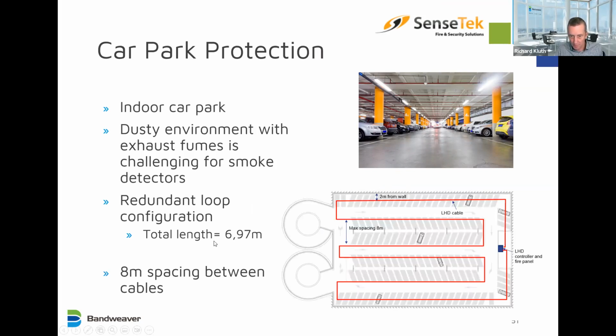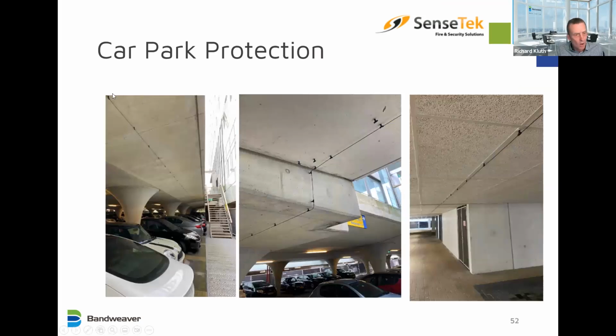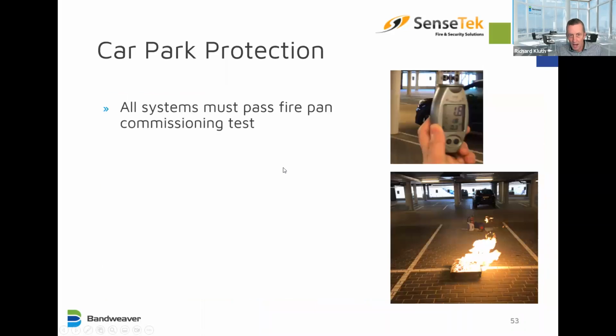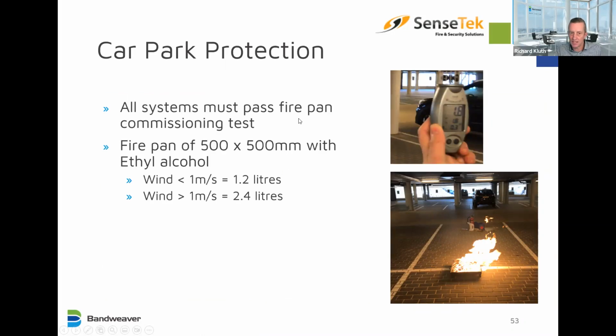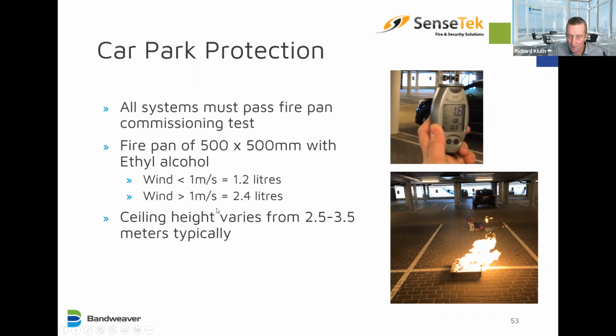spacing between the cables. We can see pictures of the cable installed at ceiling level here. You can see how it can adapt to changes in ceiling height. Very flexible cable, and you can see it in different configurations. In the Netherlands, all systems must pass the fire pan commissioning test. This is a pretty small pan, 1/2 meter by 1/2 meter, with either 1.2 or 2.4 litres of ethyl alcohol, depending on the wind speed.